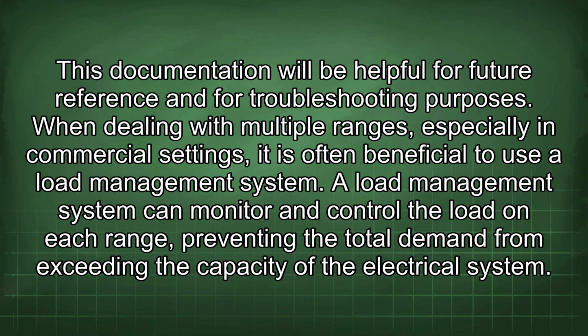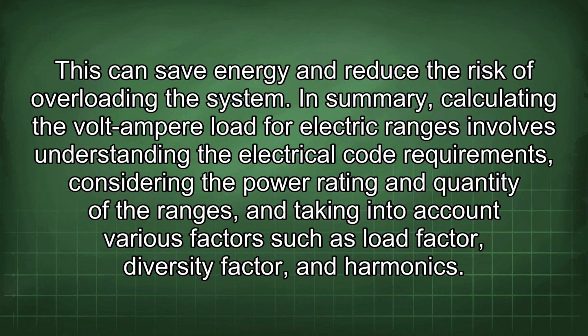When dealing with multiple ranges, especially in commercial settings, it is often beneficial to use a load management system. A load management system can monitor and control the load on each range, preventing the total demand from exceeding the capacity of the electrical system. This can save energy and reduce the risk of overloading the system.